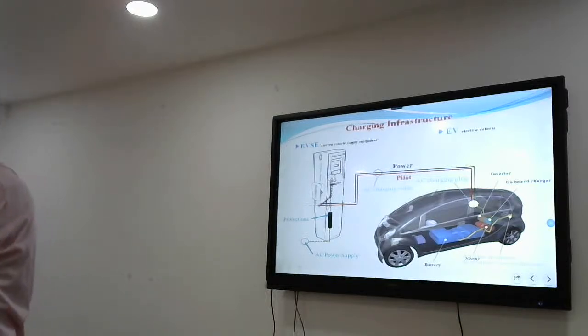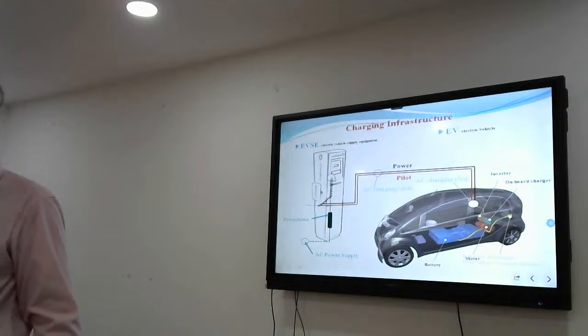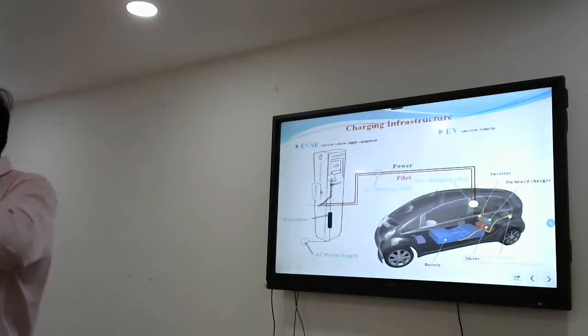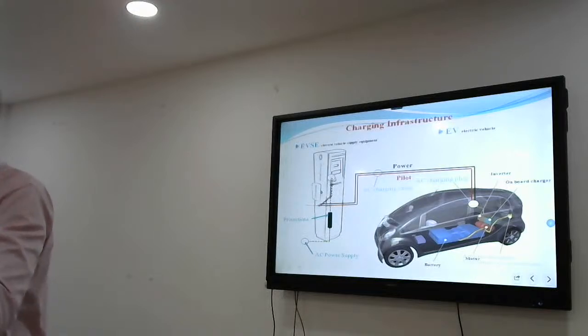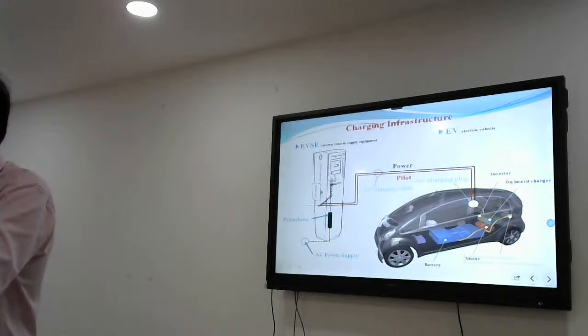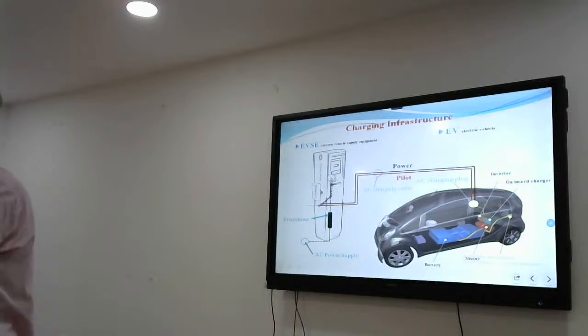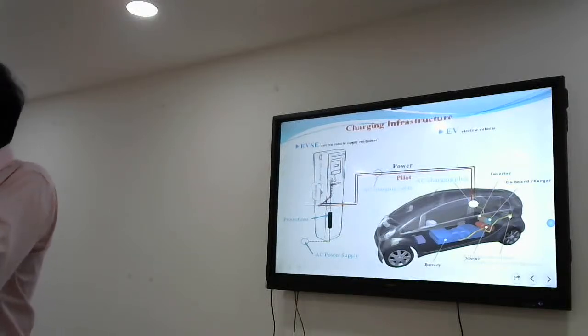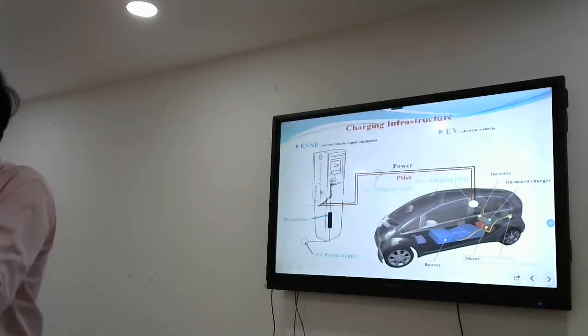In the constant voltage method, an empty battery carries more current. In the constant current method, even though the battery is 98% charged, you still send the same 5 ampere, starting and ending at 5 ampere. A fully charged battery should not get that much current, so it will damage the battery. This means CV method affects performance during the empty time of the battery, while CC method, after 98%, creates a gap that affects the cells over time.